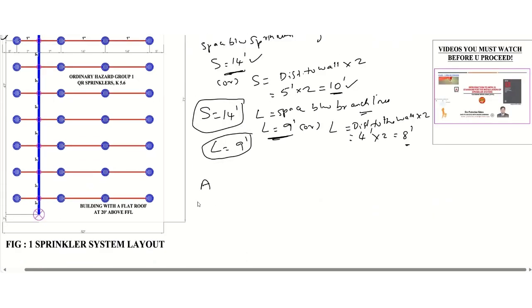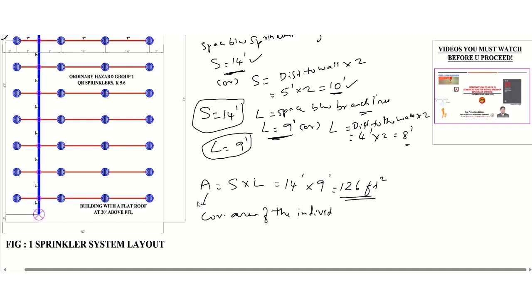The area coverage for one individual sprinkler is S by L. S is 14 feet and L is 9 feet, so the total area is 126 square feet. The area of one individual sprinkler is 126 square feet.